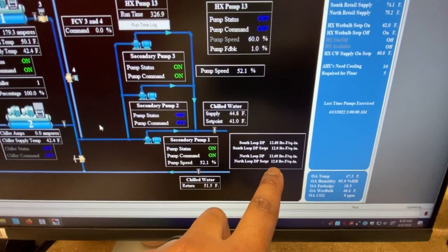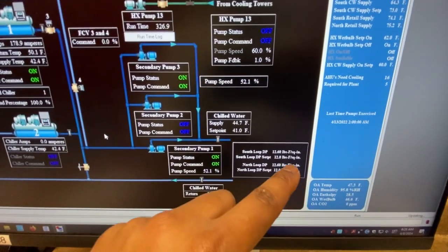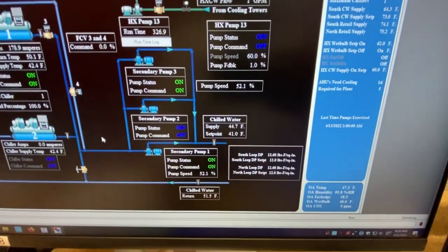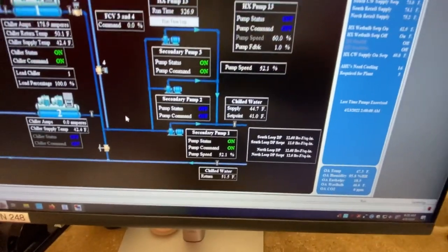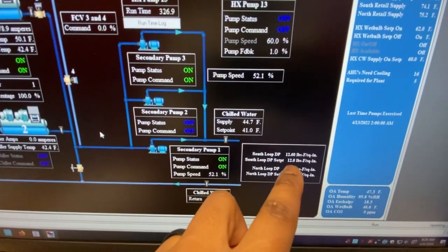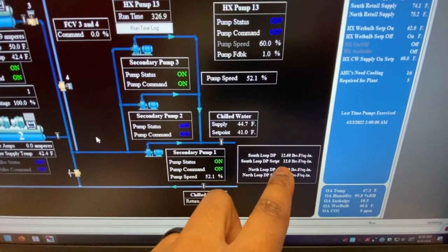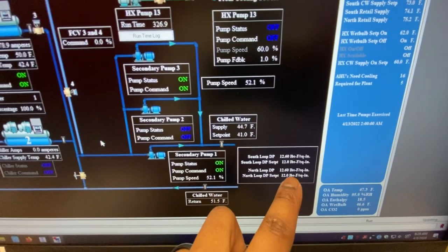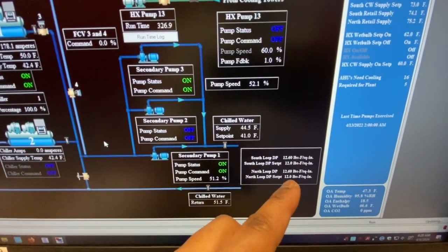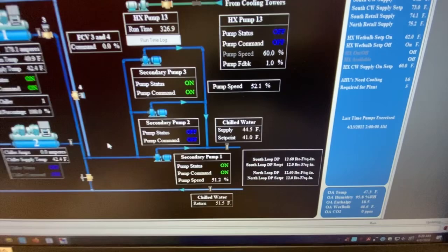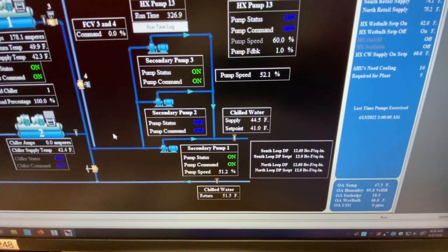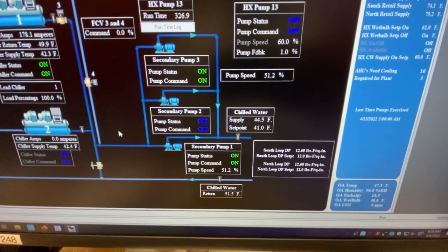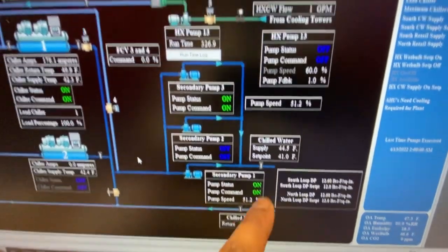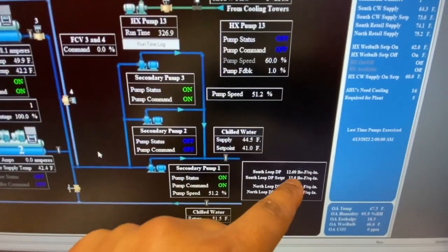For the north plant it's 12.0 as well, and we're keeping up with the DP at 12.6. As soon as you lose the DP, like right now the south plant is at 12, that's the set point for it. If I start losing the DP, going to 8, 7, whatever, that means I'm not even cooling the building anymore, I've lost the building 100%. So my main goal today is to keep the supply low and keep the DP low.